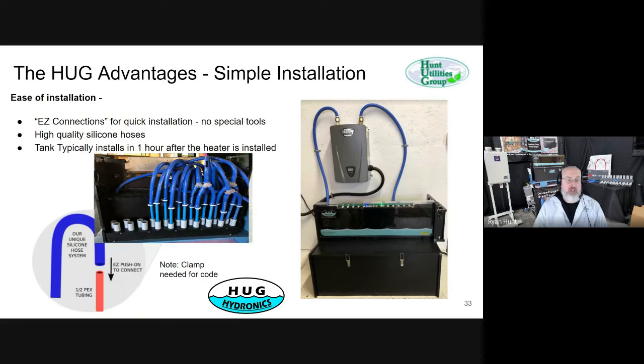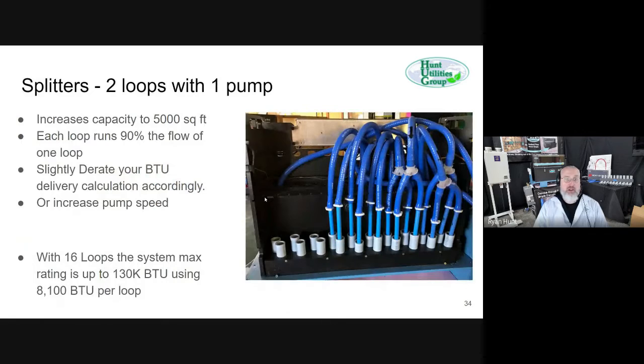The installation is pretty simple. It consists of connecting the plumbing with a very unique silicone hose system, where you just push our silicone hose over the ends of the PEX coming up out of the floor. The light blue pipes coming up vertically here are from the floor, and then the silicone hose pushes over that, and you squeeze it with a clamp, and that's the extent of the plumbing. Same with the water heater there.